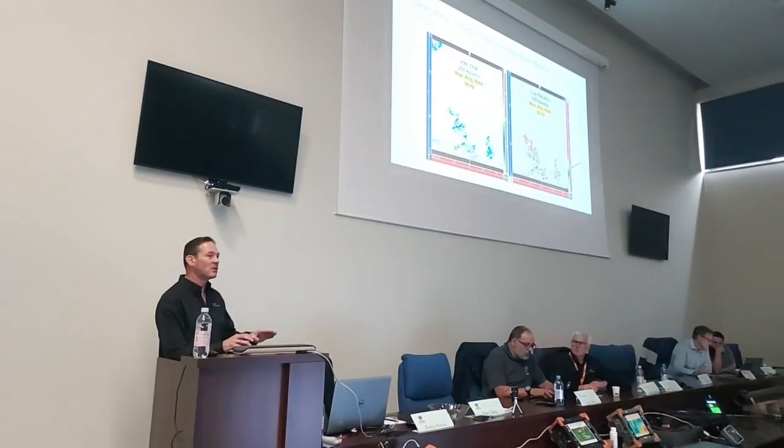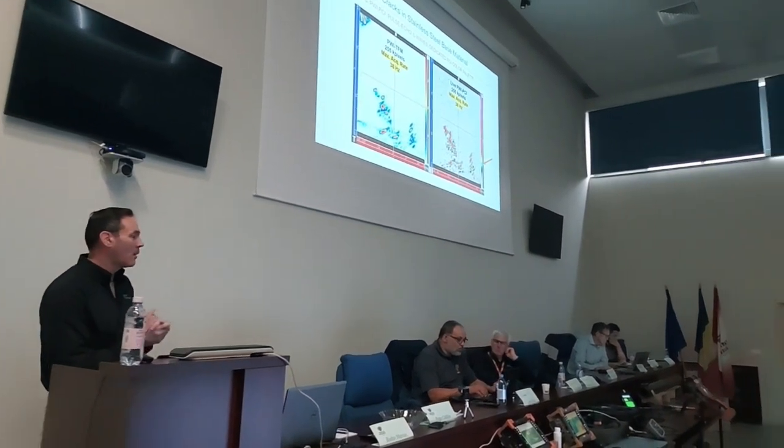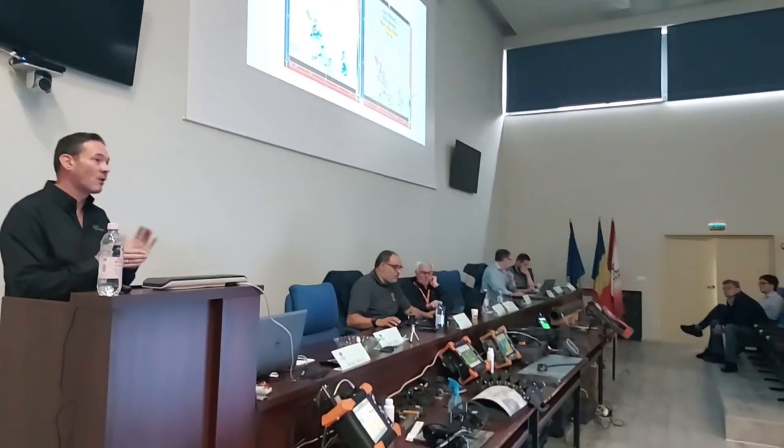Now, why is this interesting? A lot of applications in the field introduce HTHA or HIC, high temperature hydrogen attack, or hydrogen induced cracking. And what that is, is that there are delaminations or laminations being introduced into the material as it is live, and these laminations have a risk of growing together.